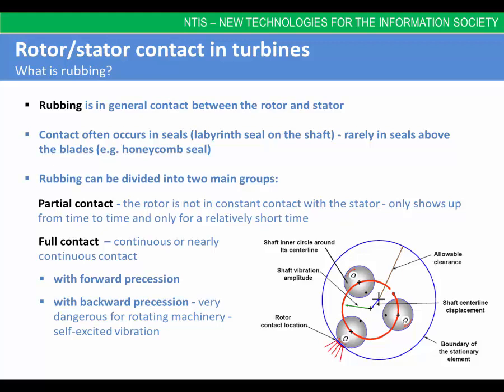The rotor-stator contact or rubbing has become a pretty common phenomenon in terms of steam turbine operation in the last couple of years. The reason is that clearances in flow paths of the turbines get smaller and smaller along efforts towards efficiency increase. In the first phase, especially seals arranged between the rotating and stationary parts are abraded, and as a result the amount of leaking medium increases and therefore the turbine efficiency decreases.